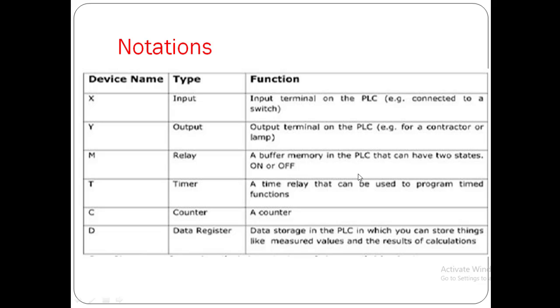Now let's look at notations — how we denote Mitsubishi PLC inputs, outputs, and other things. Input is denoted with X, output is denoted with Y. M is a relay or buffer memory in the PLC that can have two states: on and off. T is used for the denotation of timer — a time relay used to program time functions. C is used for counter. D is a data register for data storage in the PLC, in which you can store measured values and results of calculations.